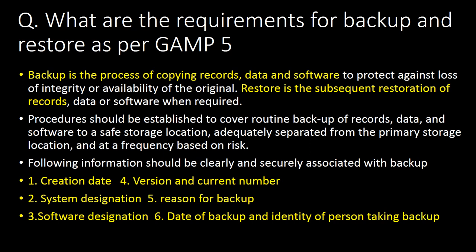The following information should be clearly and securely associated with the backup: first, creation date; second, system designation; third, software designation; fourth, version and current number; fifth, reason for backup; and sixth, date of backup and identity of the person taking the backup.